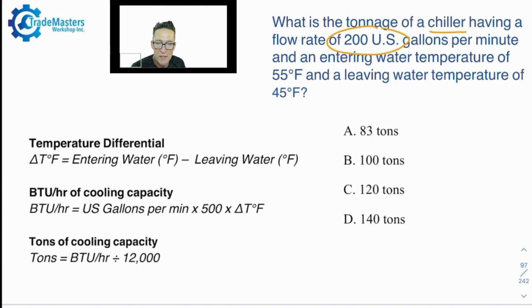So we need one equation, and here it is. Q, which is going to be your BTUH, or your number of BTUs, actually. Q is going to be equal to your gallons per minute, so GPM, and I want to write here US because this equation is for US gallons. If anytime you're asked about imperial gallons, just multiply everything by 1.2. And that's going to be multiplied by a constant, which is the number 500. Don't worry about it, just accept that it is the number 500. And then we multiply by the change in temperature across our barrel or our coil.